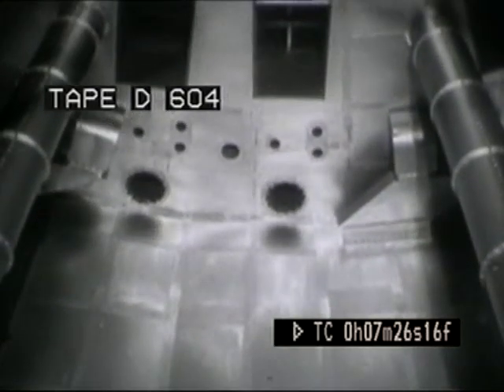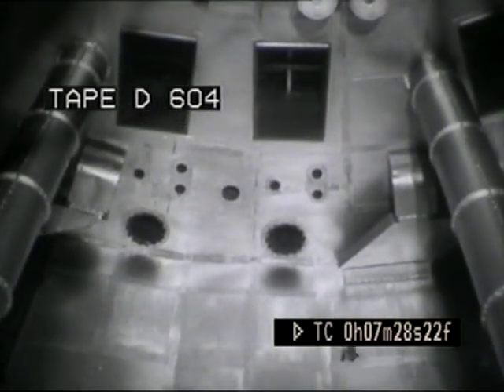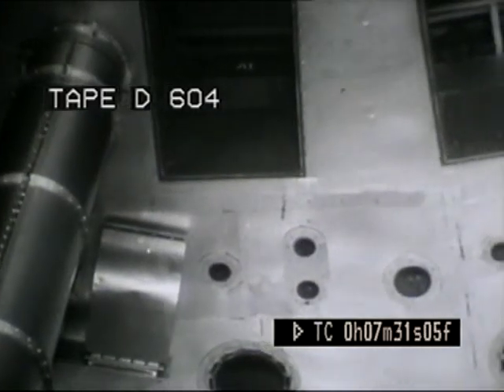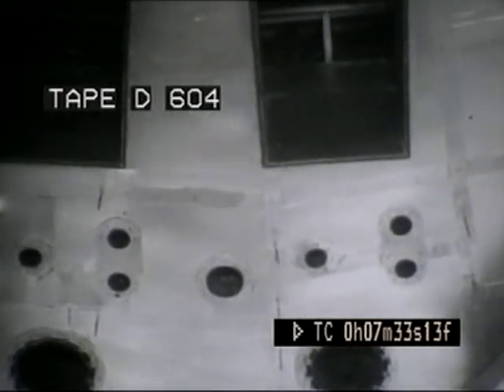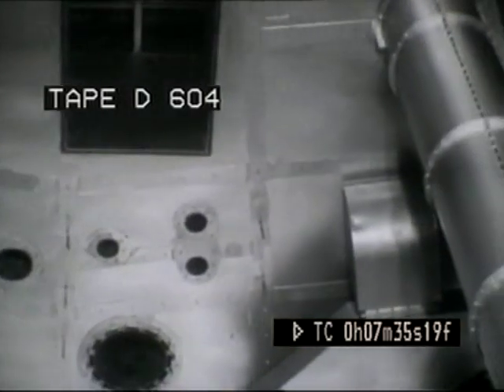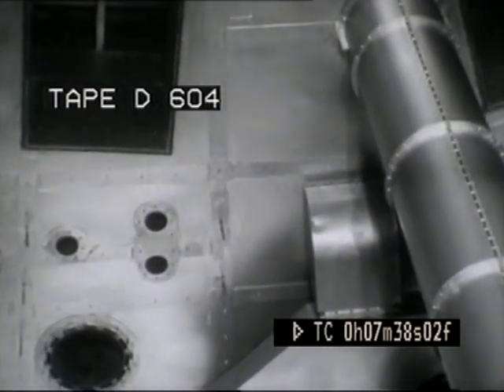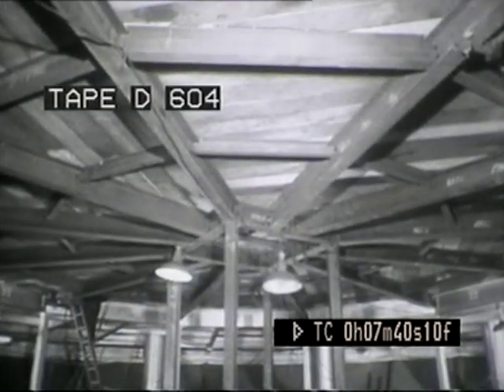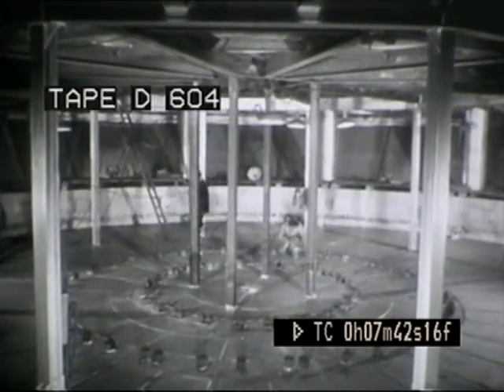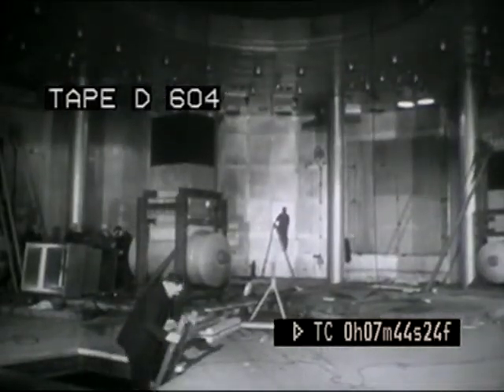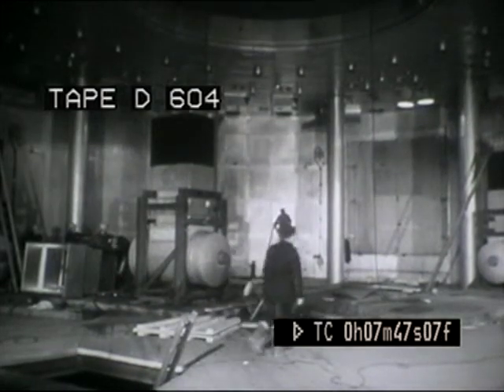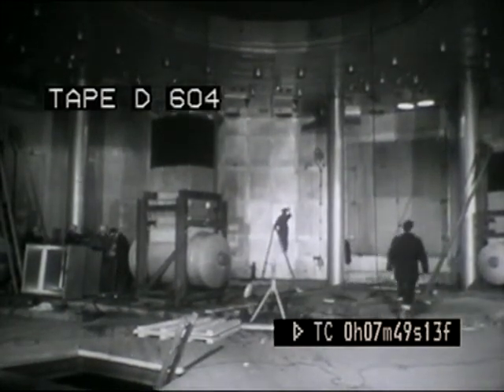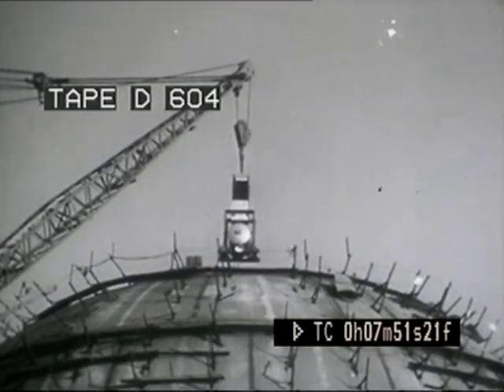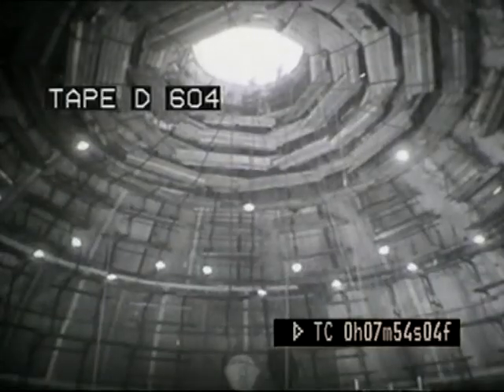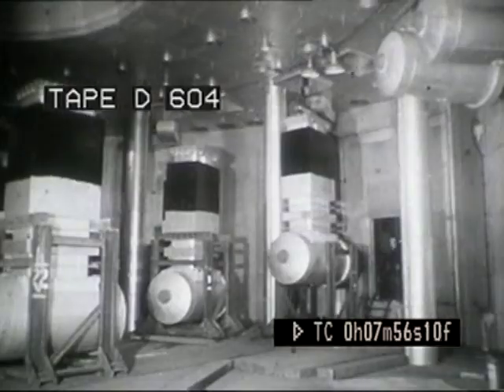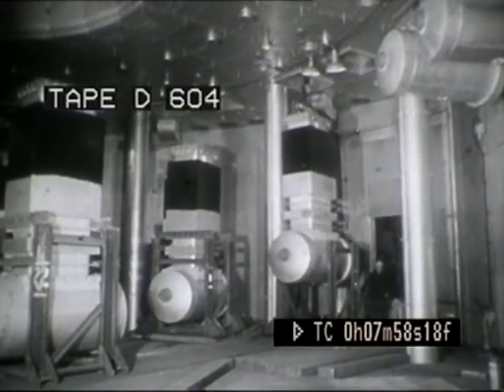In the roof of the vault were set the liners for the 24 electromagnetic pumps to be installed as part of the primary heat exchanger circuit. As the vault was 36 feet high internally, a temporary floor 10 feet above the base was erected to assist in the installation of these pumps and other equipment. Each pump had to be lowered by crane through the top of the sphere down to the temporary floor, skidded across to its position, and then hoisted up.